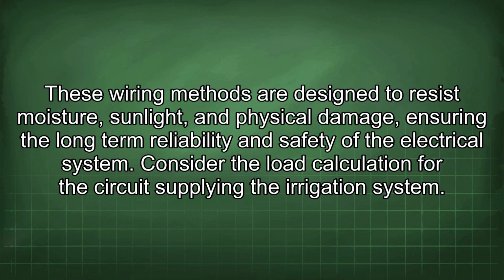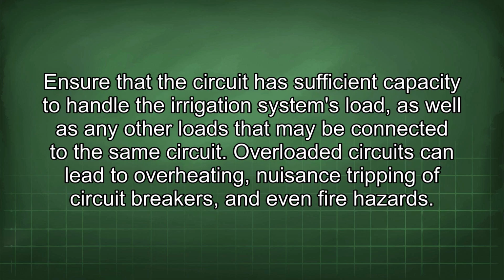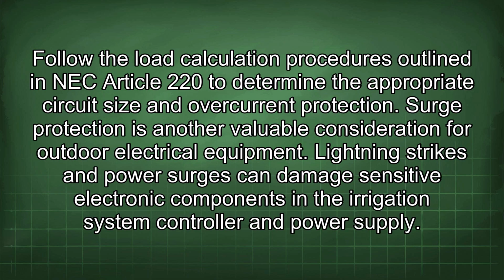electrical system. Consider the load calculation for the circuit supplying the irrigation system. Ensure that the circuit has sufficient capacity to handle the irrigation system's load, as well as any other loads that may be connected to the same circuit. Overloaded circuits can lead to overheating, nuisance tripping of circuit breakers, and even fire hazards. Follow the load calculation procedures outlined in NEC Article 220 to determine the appropriate circuit size and overcurrent protection.